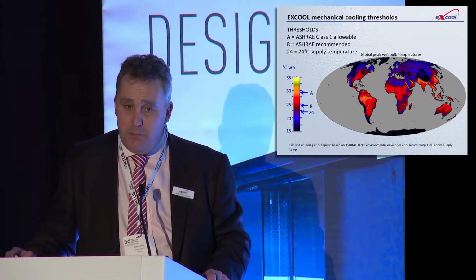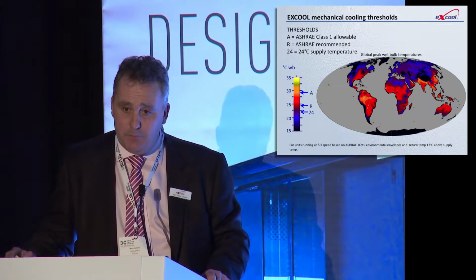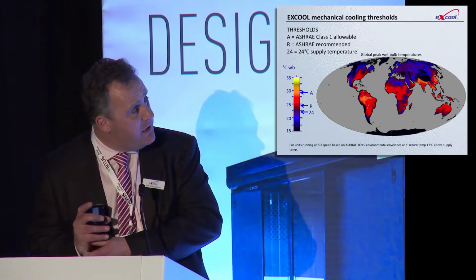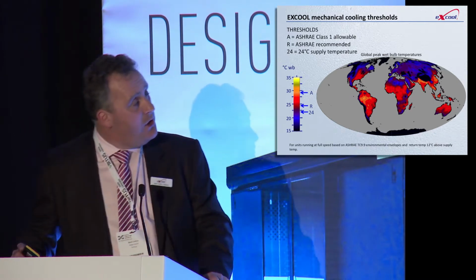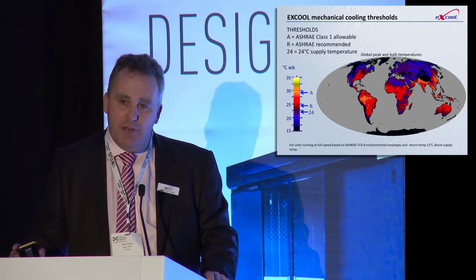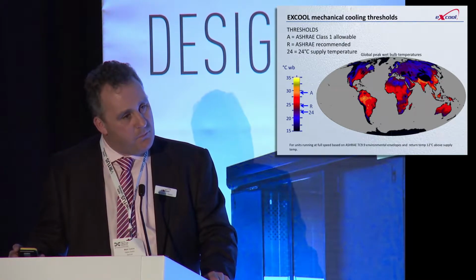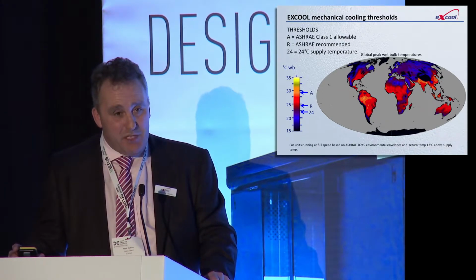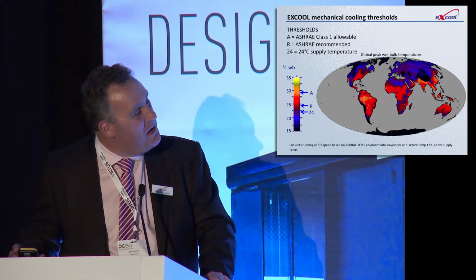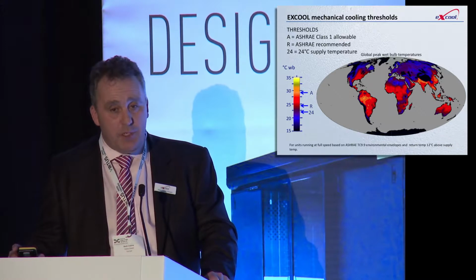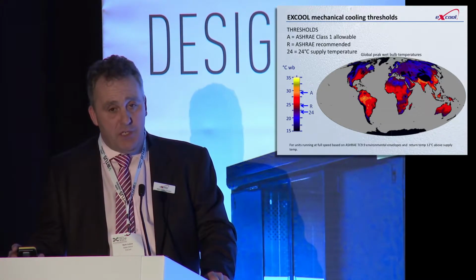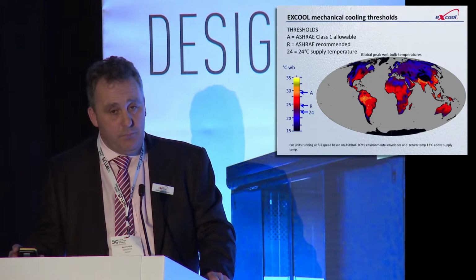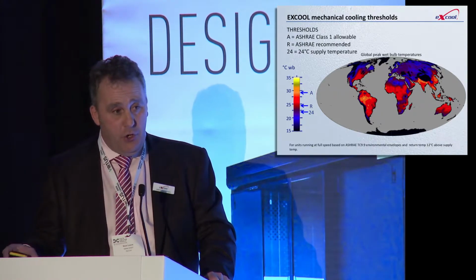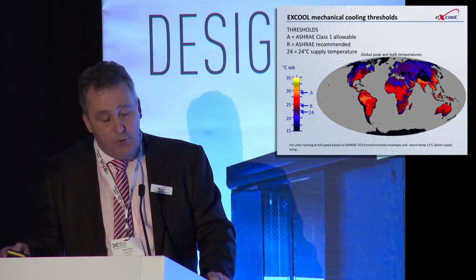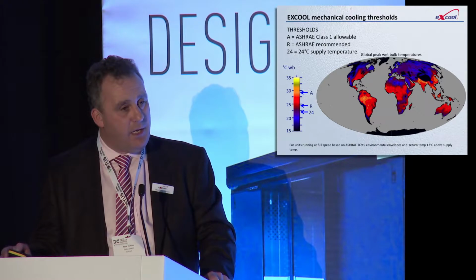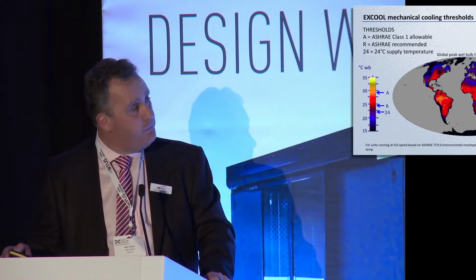Now, there's very few places in the world that exceed those outdoor air conditions. That's demonstrated on this map of the world, which is a wet bulb temperature map, which is completely different to what you'd expect to see if it was a dry bulb temperature map. And you can see there that we're able to operate Excool in the middle of the Sahara Desert without any compressors. We need a fair bit of water to do that, admittedly, during the summer, which is pretty much all the year, but we don't need compressors. Now in the UK, we are now supplying approaching 60 megawatts worth of cooling without any compressors at all. In Europe, you can see there in places like Madrid, for instance, you're able to supply air for most of the year without any mechanical cooling at all.